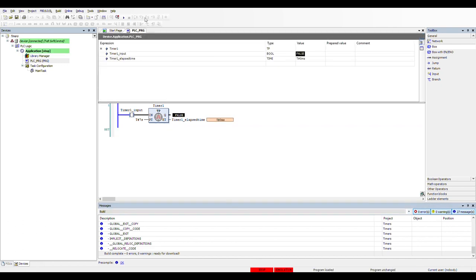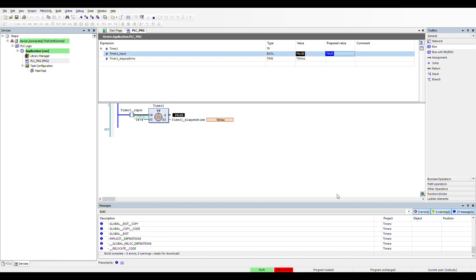I'm logging on to the simulation and putting the PLC in running mode. The input is false, so the output is also false and the elapsed time is zero. Let me turn on the input — as soon as I do, the elapsed time starts to count, and after 7 seconds the output is set to false again. So we got a pulse from the moment I turned on the input lasting 7 seconds.